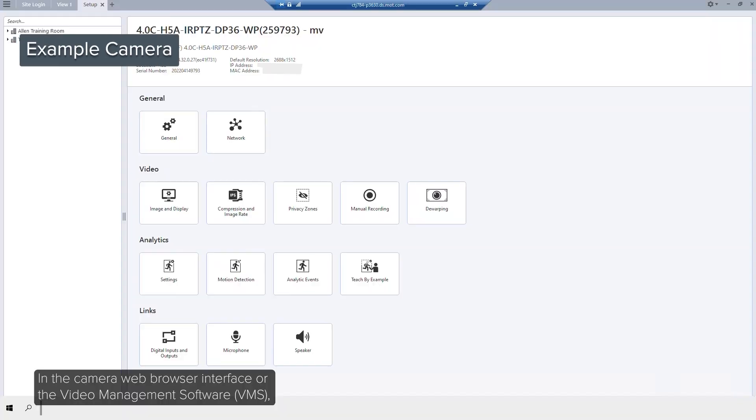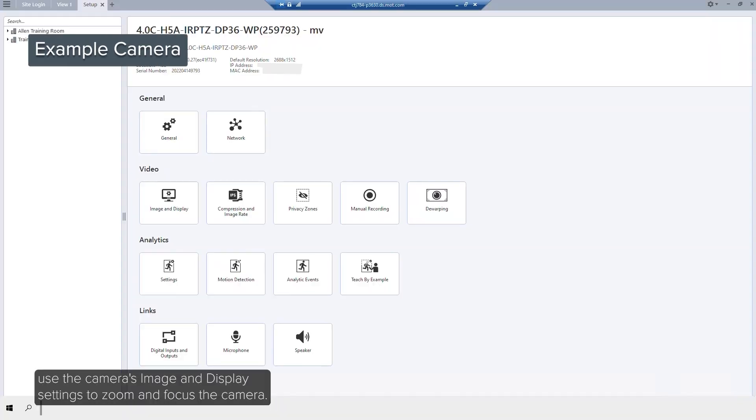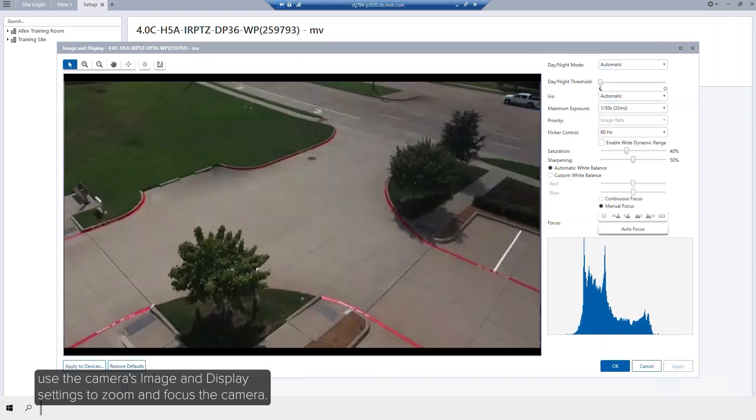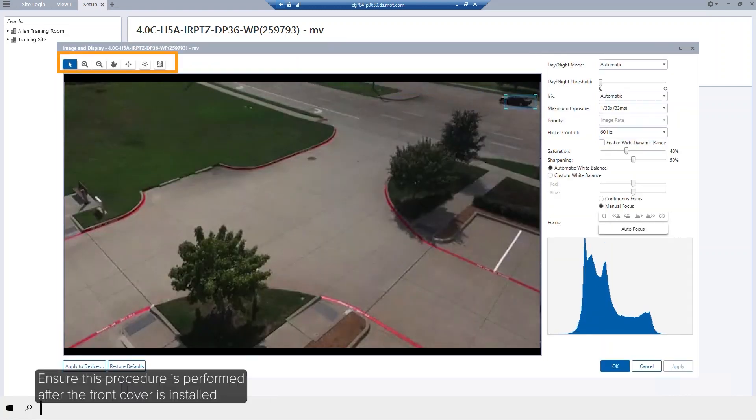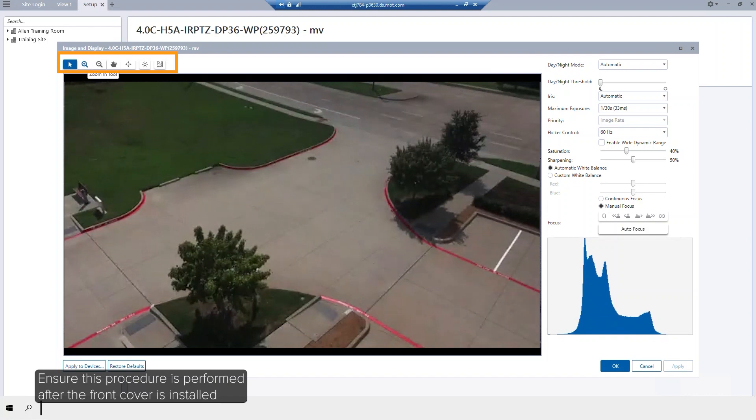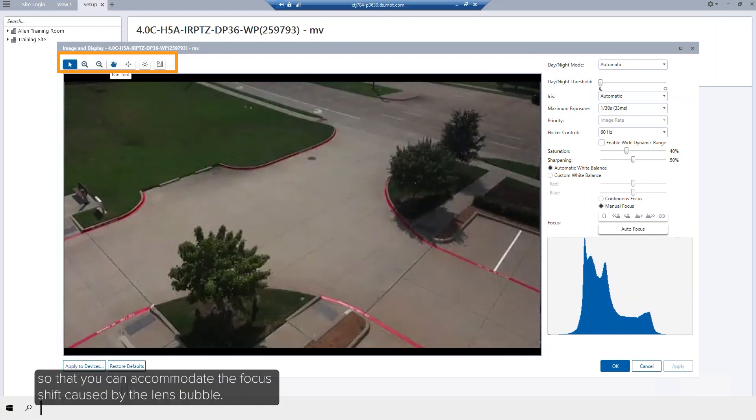In the camera web browser interface or the video management software, use the camera's image and display settings to zoom and focus the camera. Ensure this procedure is performed after the front cover is installed so that you can accommodate the focus shift caused by the lens bubble.